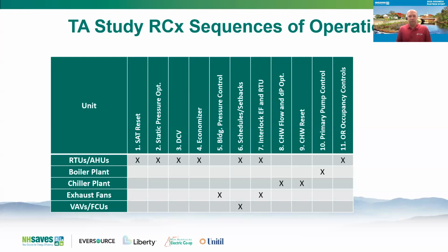Chilled water flow optimization, chilled water reset on the chiller plant, as well as primary pump control on the boiler plant. So again, just slow the primary pumps down to maintain a differential temperature. As long as you're meeting the boiler's minimum flow, it can be a great opportunity.